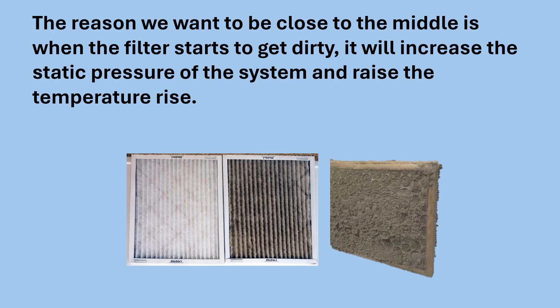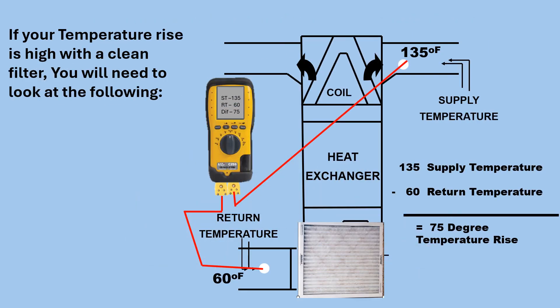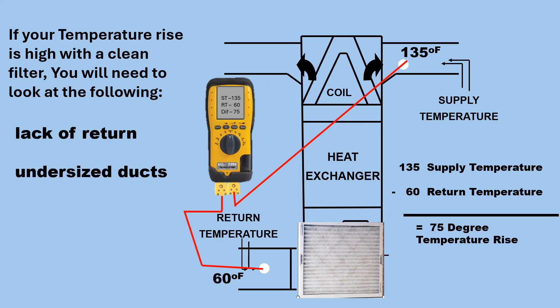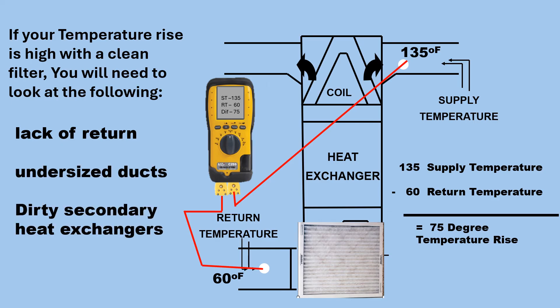The reason we want to be close to the middle is that when the filter starts to get dirty, it will increase the static pressure of the system and raise the temperature rise. If your temperature rise is high with a clean filter, you will need to look at the following: lack of return, undersized ducts, or dirty secondary heat exchangers.